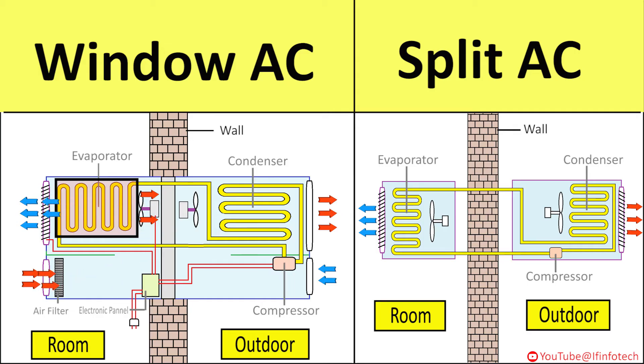The temperature of the cooling coil is much lower than the room air. The refrigerant inside the cooling coil absorbs heat from the air, which is then circulated back into the conditioned room, reducing its temperature. Due to the reduction in temperature of the air, dew is formed on the surface of the cooling coil, as the temperature of the cooling coil is lower than the dew point temperature of the air.